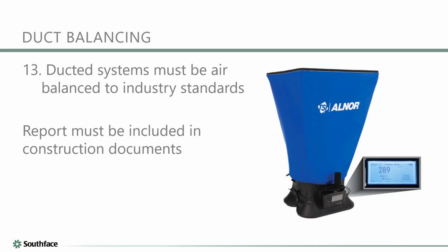Something I've seen on these light commercial buildings over time is that the contractor would be balancing the system, or so he claimed, but he's just using a thermometer, right? So he's looking for a certain temperature at a certain thermometer, and that's what he's using to balance the system, because this equipment is pretty expensive and not a whole lot of people have access to it, right? Yeah. And so God knows what you're going to find out there when a system is said to be balanced if there's not a report to go with it.